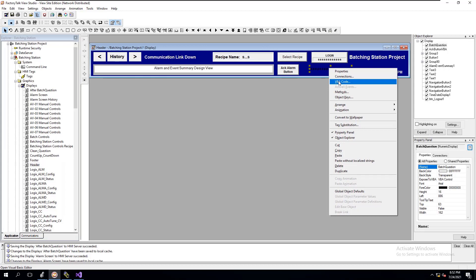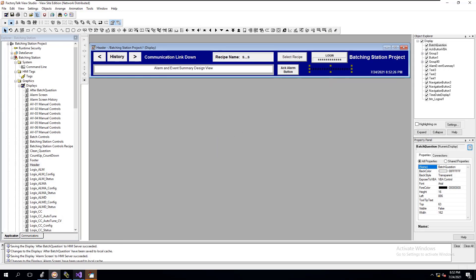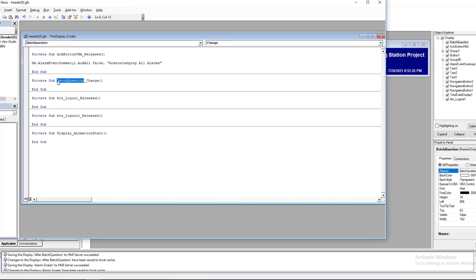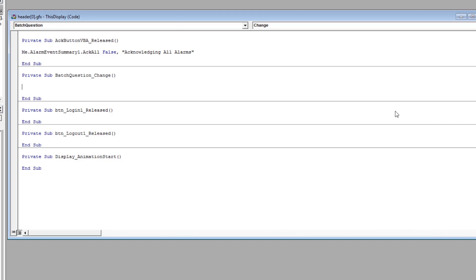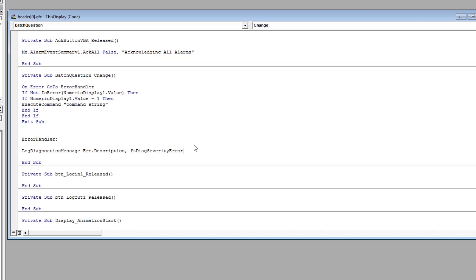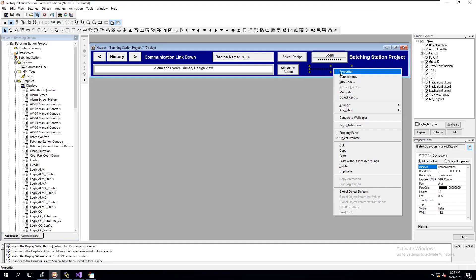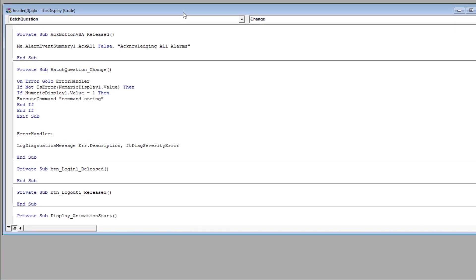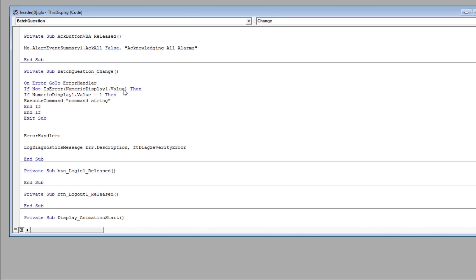Now we're going to open the VBA code. In this instance, we called the screen 'batch question' — remember, we called that 'batch question.' So right here I'm going to paste this code and we're going to change it. I'm getting this code off of the Rockwell Knowledge Base. I'm going to explain this code while we edit it. This right here is the name of the element we're using — 'batch question.' So we're going to come in here, and where it says numeric display, we're going to change that. Paste in 'batch question' — that's what we named it — and then go dot value. Same thing over here: paste that in and go dot value.